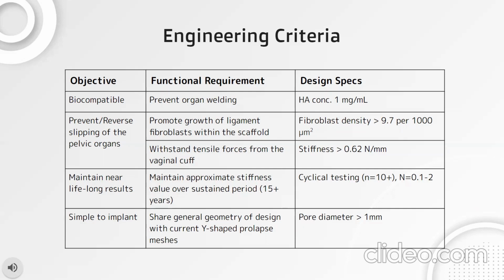Additionally, our device needs to withstand the tensile forces from the vaginal cuff, requiring a stiffness of greater than 0.62 newtons per millimeter. Third, our device must maintain a near lifelong result, so it must maintain the approximate stiffness values for 15 or more years. We'll ensure this specification by performing cyclical testing to give us a more accurate view of the device's tensile strength over time. Finally, this device needs to be simple to implant. To prevent any unnecessary learning curve for physicians, our device will share its general geometry with current Y-shaped mesh designs, including a pore diameter of greater than 1 millimeter for easy suturing.